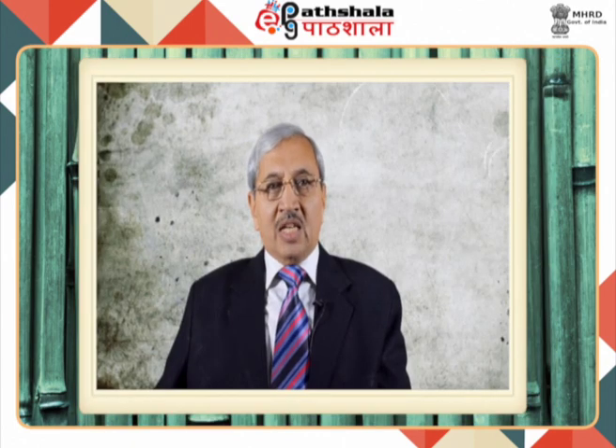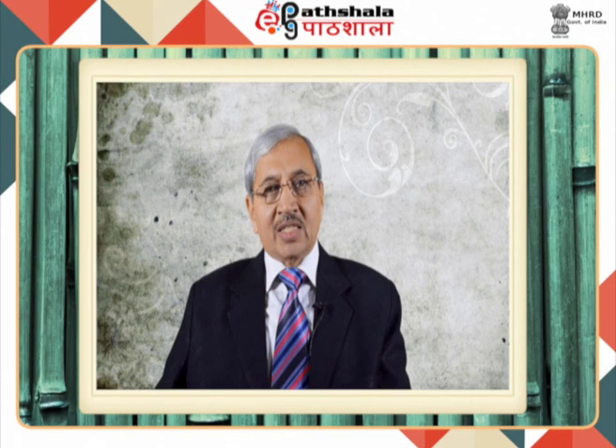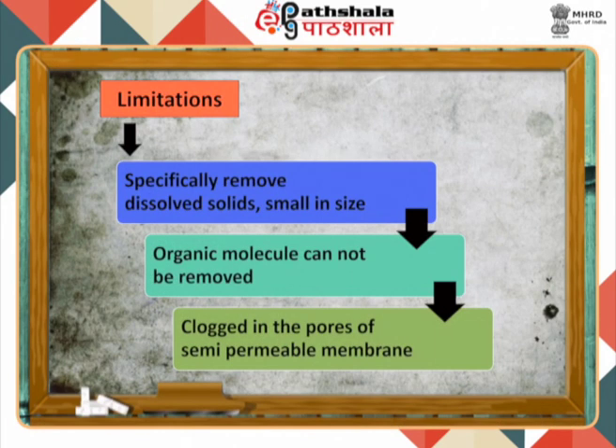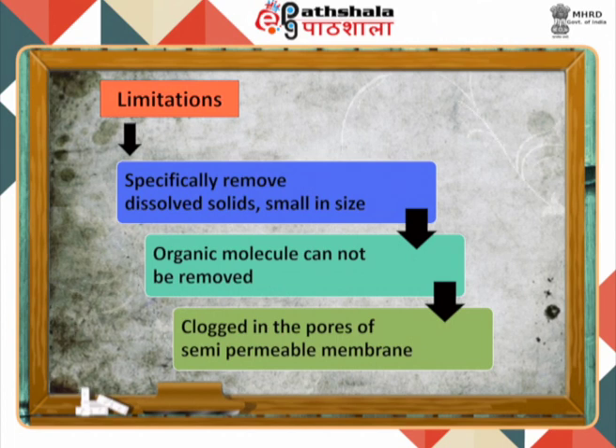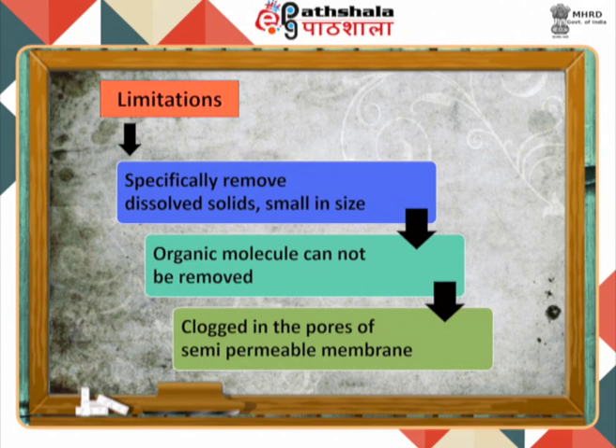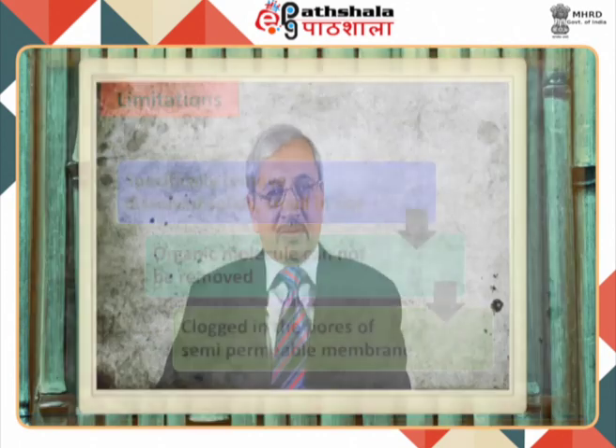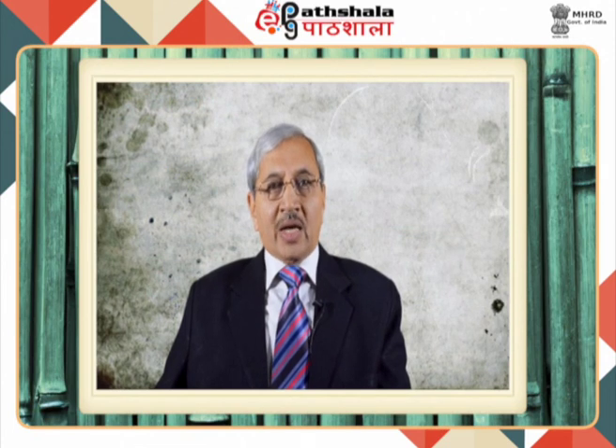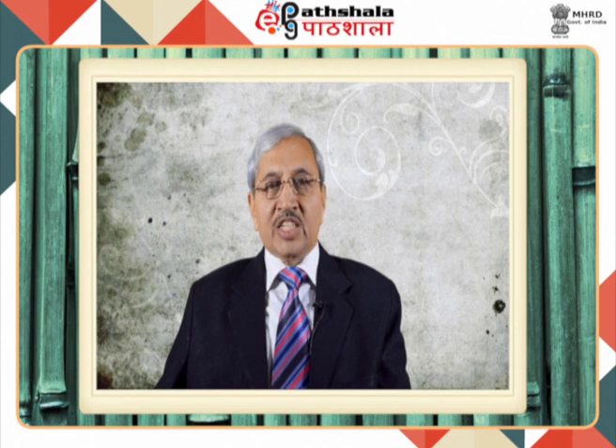But there is a limitation of using electrodialysis, as it is particular to dissolved solids which are small in size. Therefore, organic molecules cannot be effectively removed by it, as they are larger in size than inorganic molecules and clog the pores of the semipermeable membrane. There is another drawback, as it requires high energy for desalination of concentrated feed solutions.